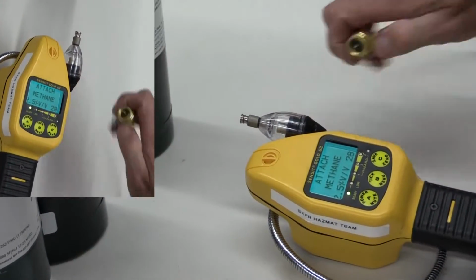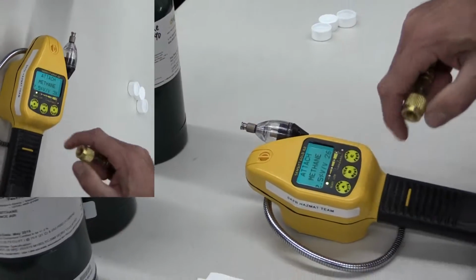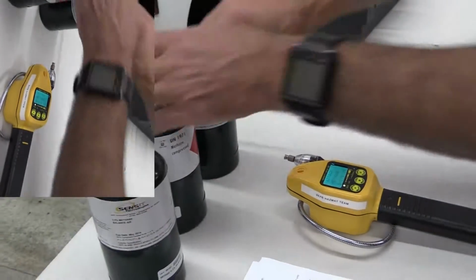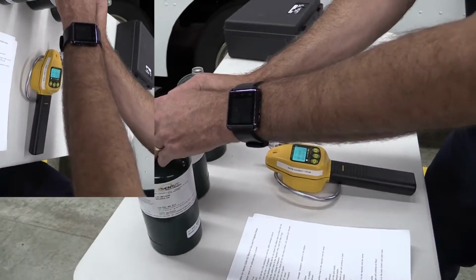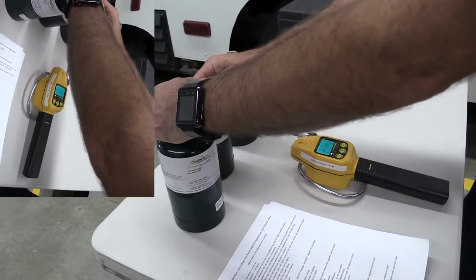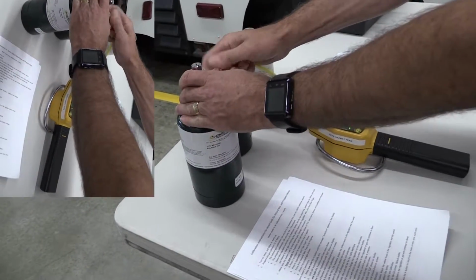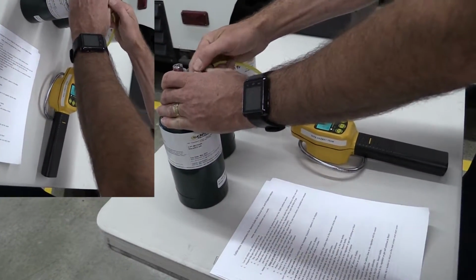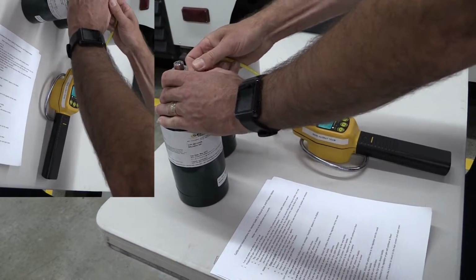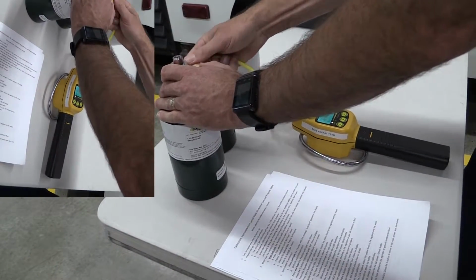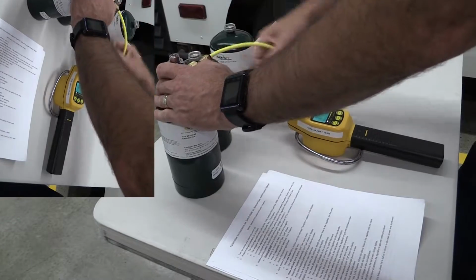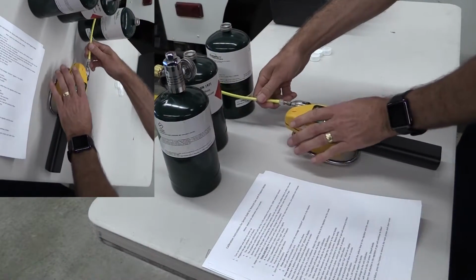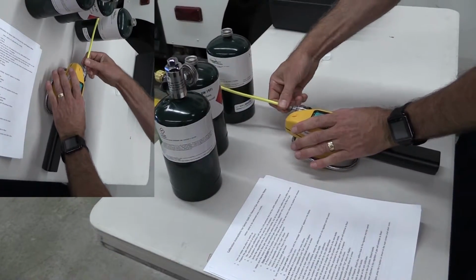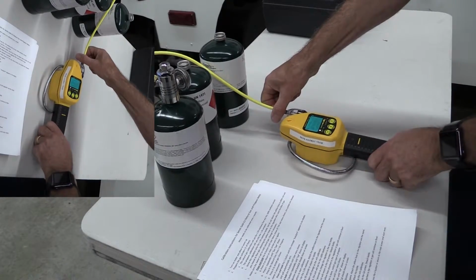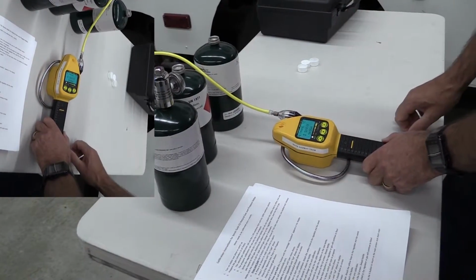It's telling us to attach the 2.5% methane solution. You only have 30 seconds in which to do this. So screw the hose onto the regulator. Remember that as soon as this is attached, gas is now flowing out this end, and attach this end to the unit. Once it senses that it's there, it'll start running numbers on the screen.